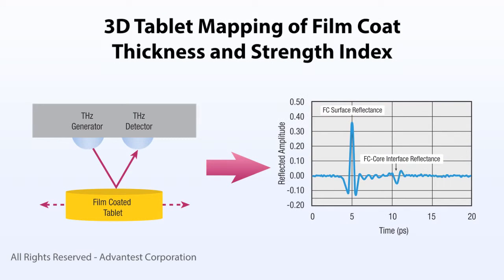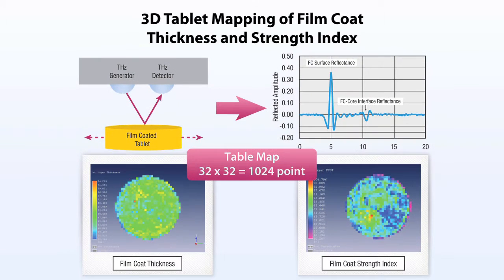Three-dimensional mapping is achieved by recording a trace for each discrete spot in the array covering the tablet surface. The 3D map shows the spatial uniformity of film coat thickness, and additional parameters, such as film coat strength, can also be derived from the same dataset.